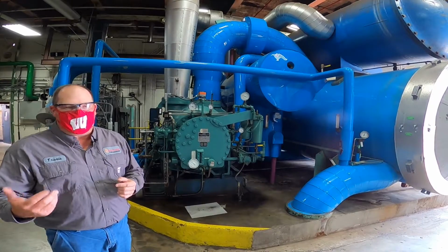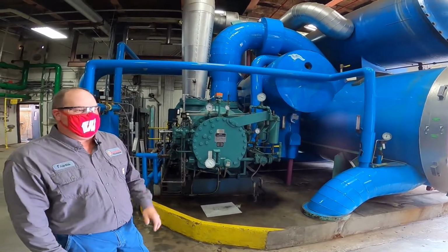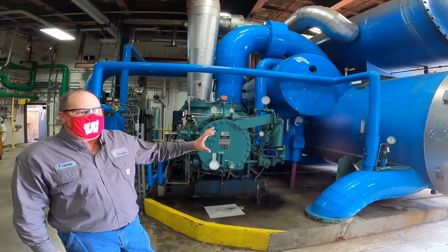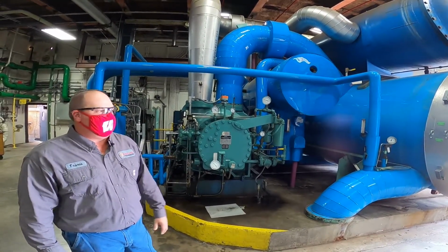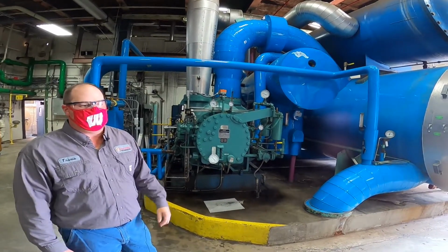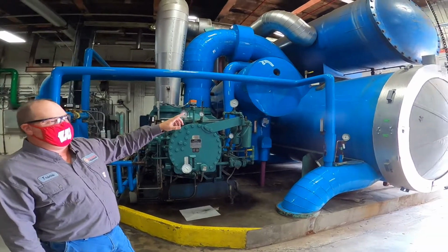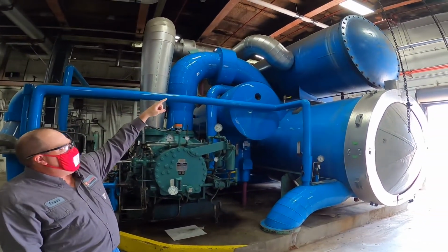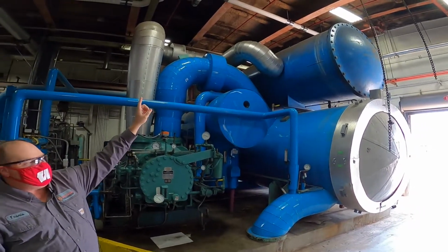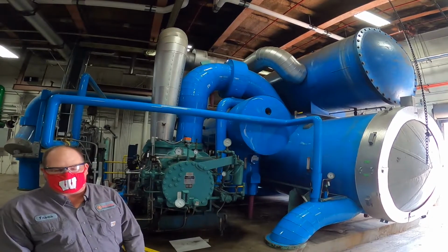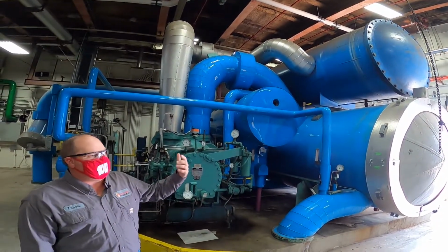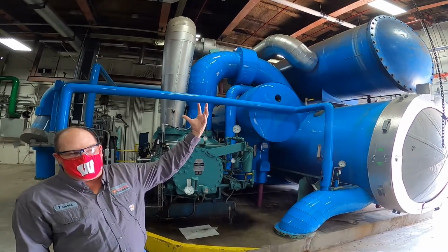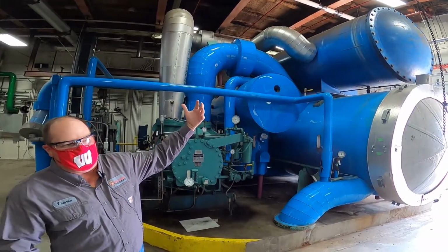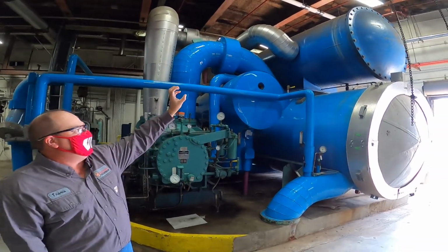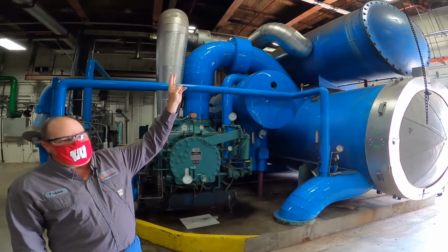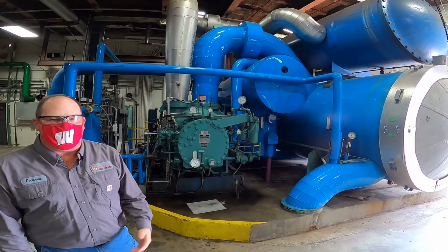And on the real hot, humid days, what we call design days, when we have 85-degree wet bulb, the water coming back is about 55, 56 degrees, and we're putting out 40 to 42 degrees of chill water to the campus. The Freon takes the heat from the evaporator and transfers it up to the refrigerant condenser, and then on top of the heating plant, you see a big cooling tower, and that's using lake water. That lake water is pumped through the condenser to absorb the heat that the Freon is carrying. It's actually the water absorbing the heat, not the Freon. The Freon's just carrying it. And we take that heat, pump it up to the cooling tower, and then it evaporates in the atmosphere.